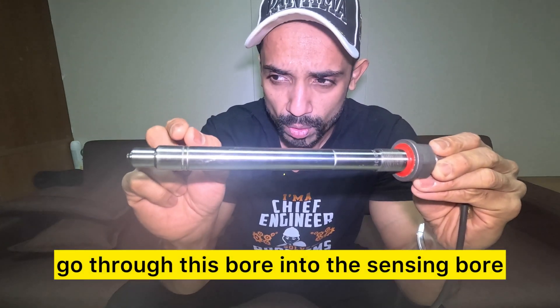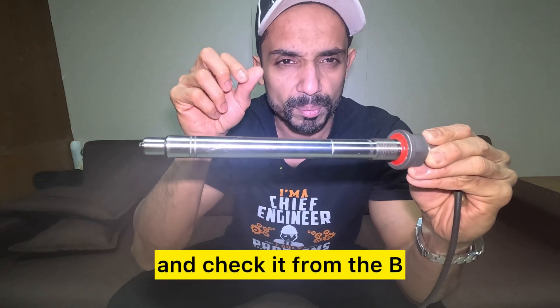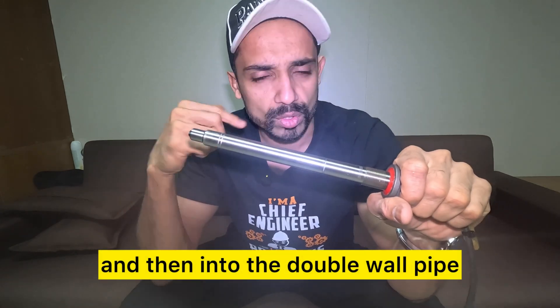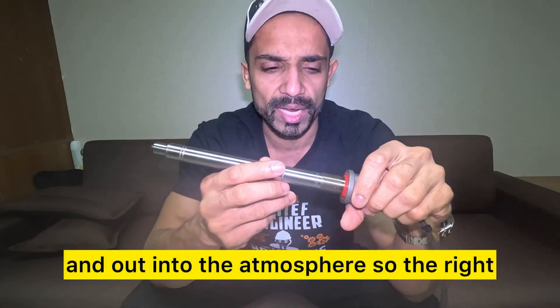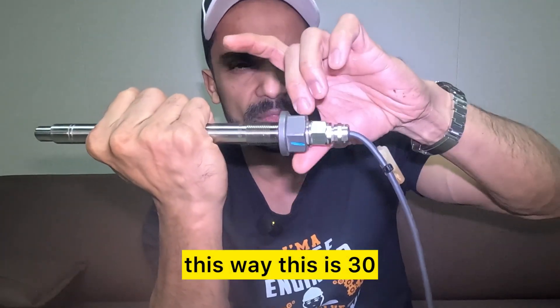The leaks will go through this bore into the sensing bore where we can detect and check from the B and D ports — the block and detect ports — and then into the double wall pipe and out into the atmosphere. So loosen the lock nut all the way out — this spanner is 30mm and this one is 19mm.